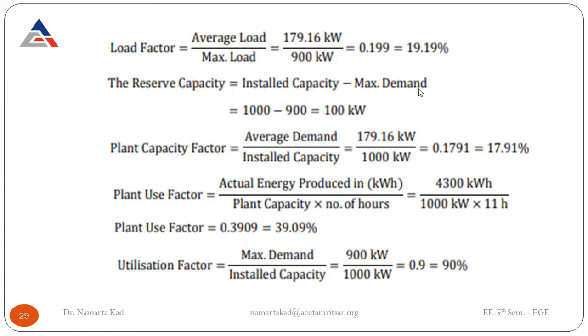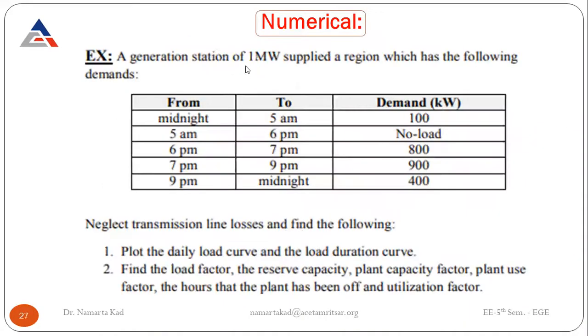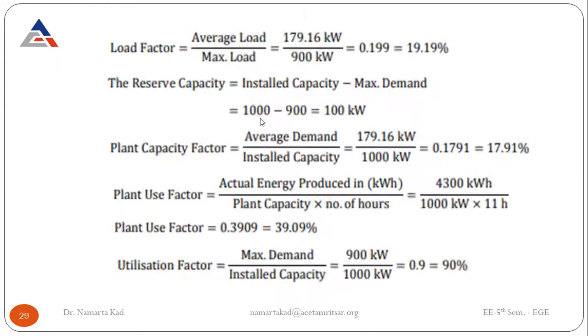Reserve capacity = installed capacity minus maximum demand. Installed capacity is 1000 kW (1 MW), maximum demand is 900 kW, so reserve capacity = 100 kW. Plant capacity factor = average demand / installed capacity = 179.16 / 1000 = 0.1791.